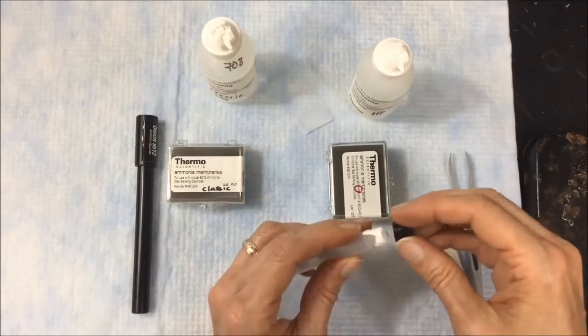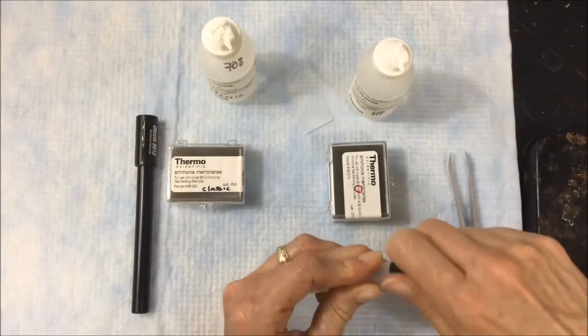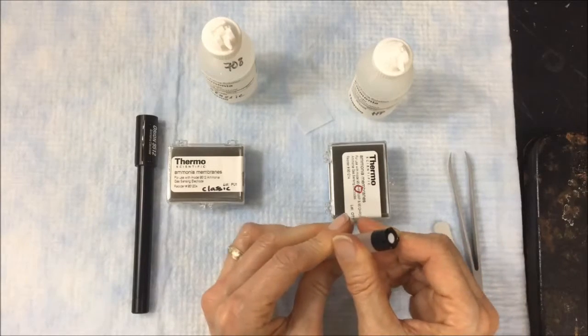Apply the cap. And here we have it—a brand new membrane installed. The body is ready to be filled with the appropriate fill solution.